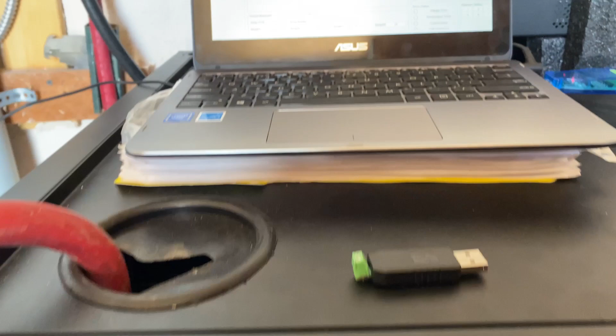As it rescans, you'll see that now it only recognizes pack 2 — it's not recognizing the other 2 batteries that are daisy chained together. So right now, the way this works is you can only monitor one battery at a time by changing the Ethernet cables. These daisy chain cables are basically useless at this point, so I'm going to disconnect them.